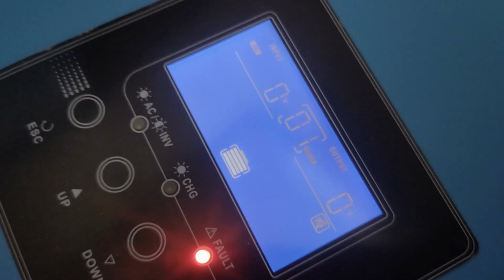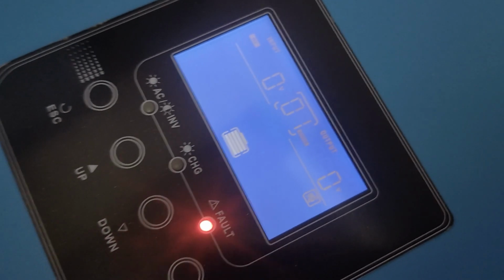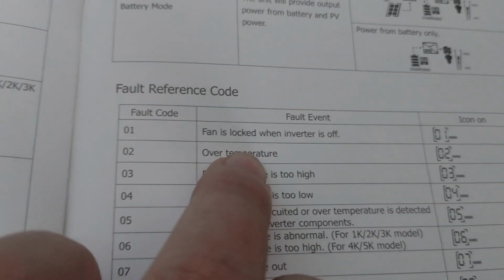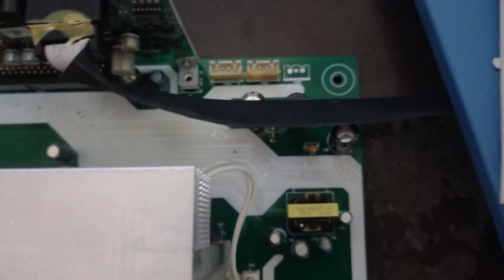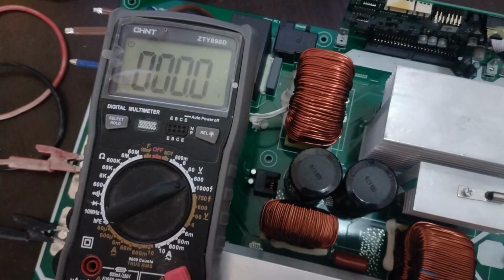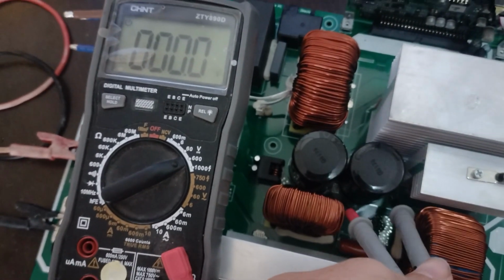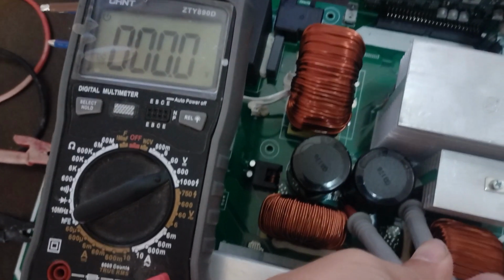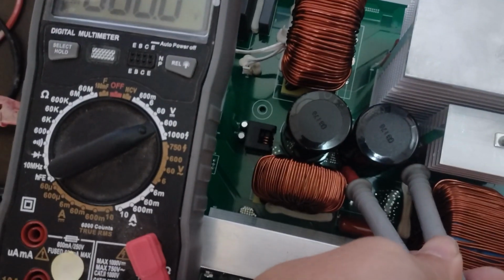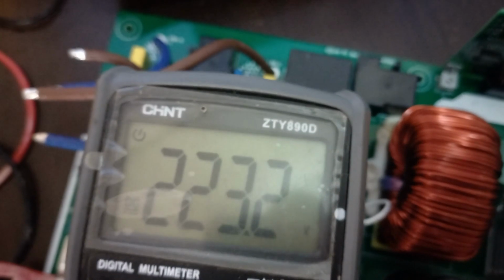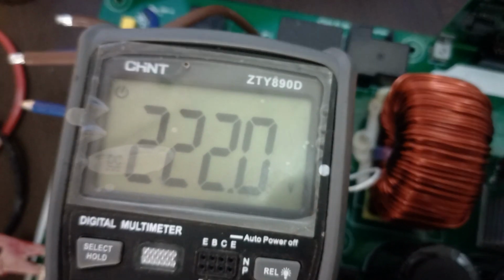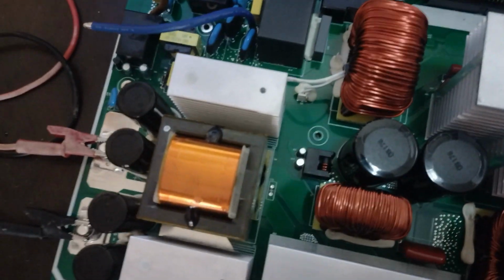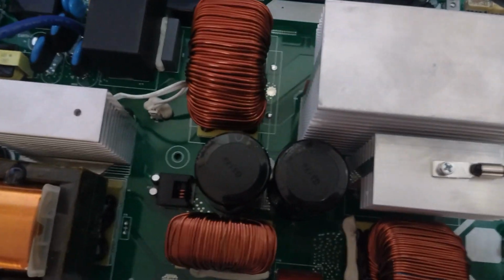Okay, new fault, fault 01. It's progress. And fault 01 is fan locked when inverter is off, and that is because there's no fans plugged in. So there's no RPM signal from the fan, so that's throwing an error. So I might go ahead and just fit the new IGBT and install this back into the chassis, and we'll see how it goes. And just as a quick check to see if that was the cause of the short on the bus, we'll probe the high voltage now. If we can get to it. There we go. And that is decaying, but yep, there was high voltage there on the bus. So that was the issue, and replacing that should hopefully get it back to life.